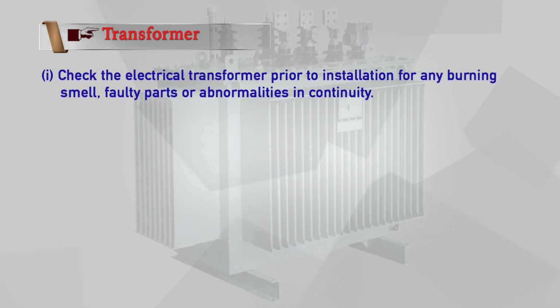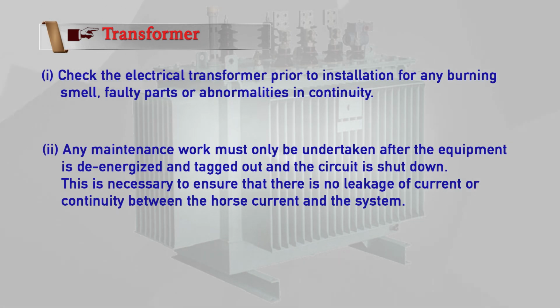So what are these transformer safety tips? The first tip is to check the electrical transformer prior to installation for any burning smell, faulty parts or abnormalities in continuity. Second, any maintenance work must only be undertaken after the equipment is de-energized and tagged out and the circuit is shut down.